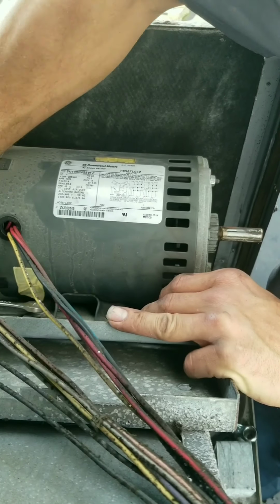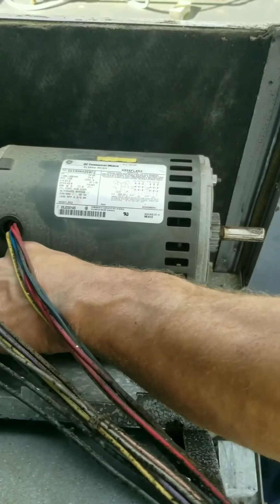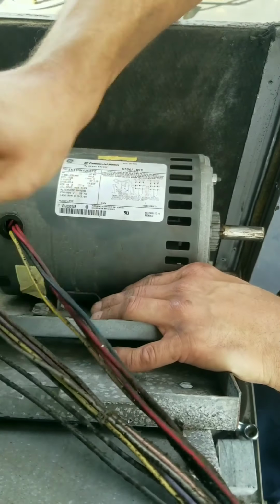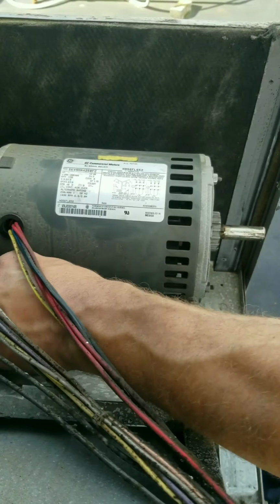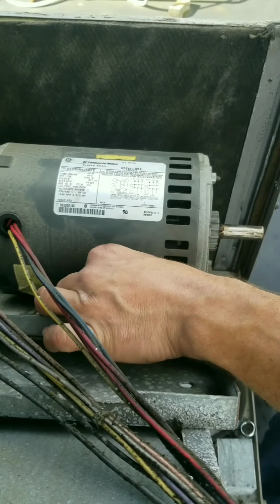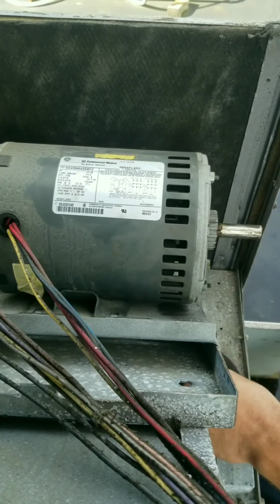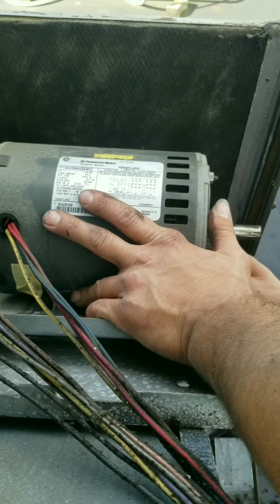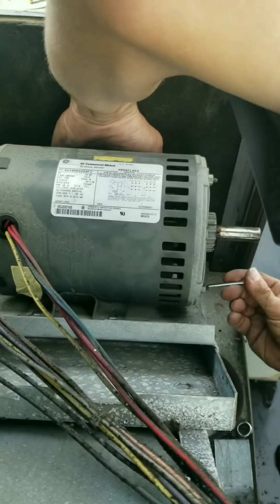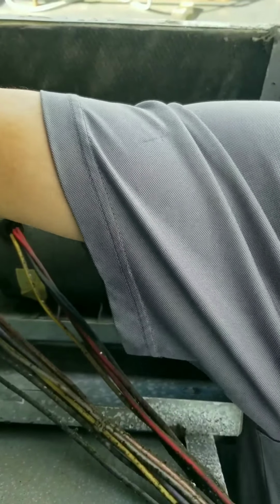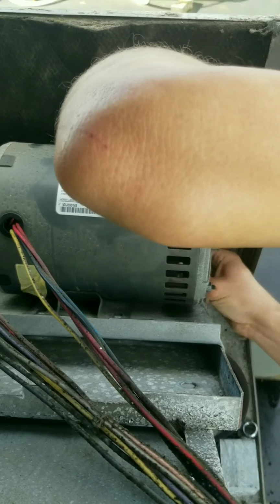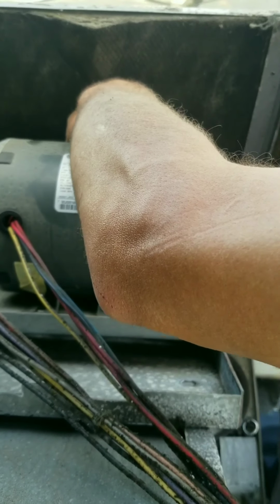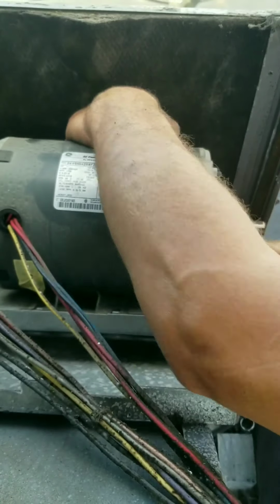In here with it, I can smell the motor is burnt up pretty good. Did verify there is some refrigerant in this thing. I didn't turn it back on, but because of all the condensation on the compressor, I would assume it froze up like that on a freeze stat. So I'm assuming the compressor pumps as long as there's no more damage to it. Bolts are tight.